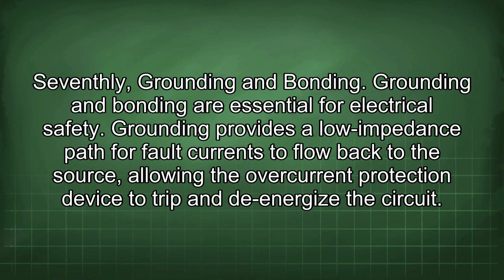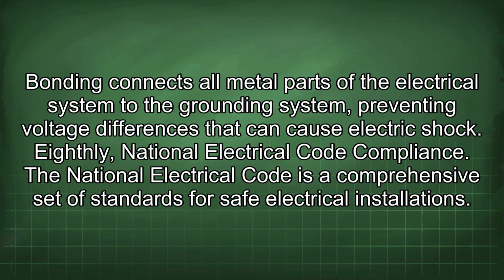Grounding and bonding are essential for electrical safety. Grounding provides a low impedance path for fault currents to flow back to the source, allowing the overcurrent protection device to trip and de-energize the circuit. Bonding connects all metal parts of the electrical system to the grounding system, preventing voltage differences that can cause electric shock. Eighthly, National Electrical Code compliance.